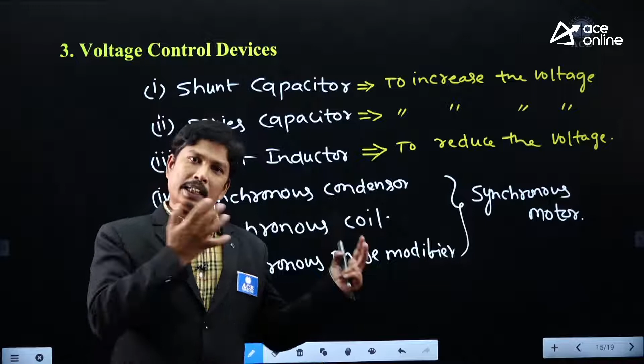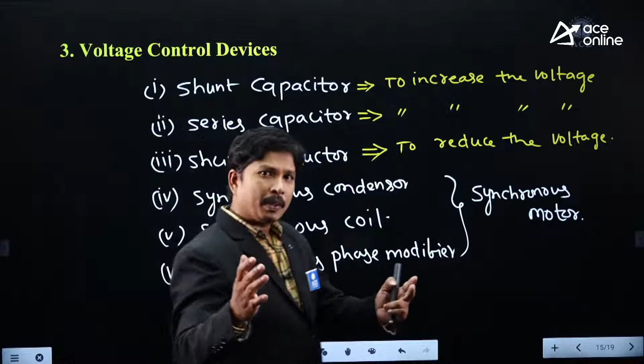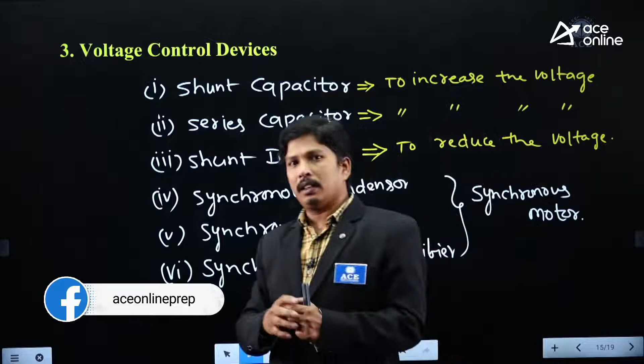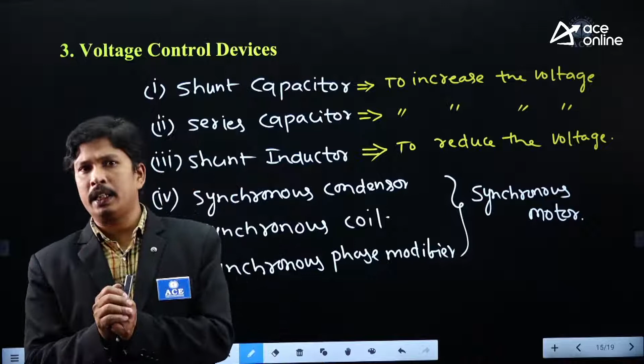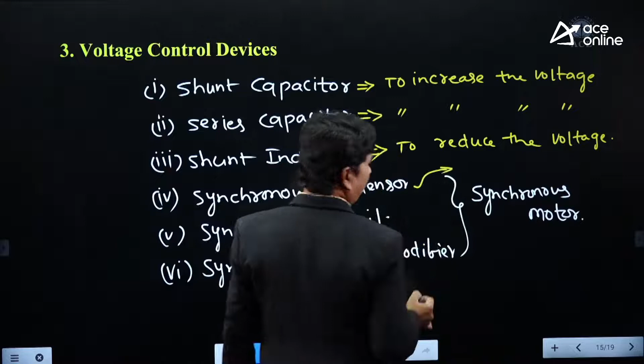And coming to the shunt inductor, it is used to reduce the voltage, to reduce over voltages. Actually, we are controlling the receiving end voltage, right? So if the receiving end voltage needs to be reduced, it has an over voltage. It has more voltage than the sending end voltage. The phenomenon whenever the receiving end voltage is more than the sending end voltage, we call it the Ferranti effect. It may occur at no load conditions or lightly loaded conditions. Now in those conditions, to reduce those over voltages, we go for shunt inductor or shunt reactor connections. And coming to the synchronous condenser, it is an over-excited synchronous motor.